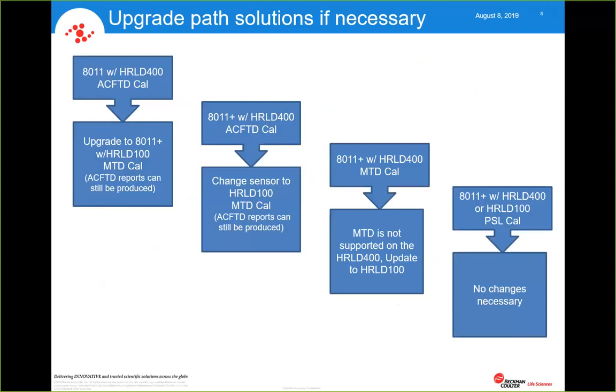If you have, in the third option, an 8011 Plus with an HR LD400 MTD cal, which you really shouldn't have, but some of the old, way old HR LD400s had a little bit better sensitivity than the new ones when we transitioned to the new laser diode. The bottom line is, the MTD is not supported on the HR LD400, so we simply have to upgrade the sensor to an HR LD100 sensor, and then it would be good to go from that point on.